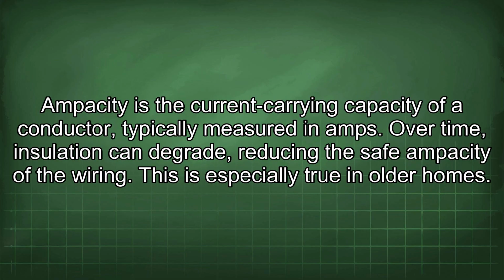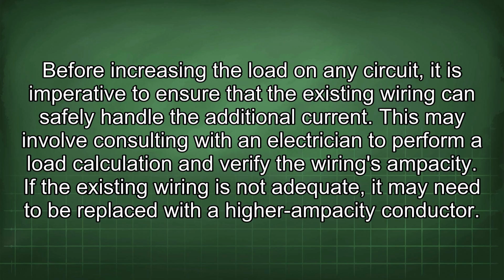Ampacity is the current carrying capacity of a conductor, typically measured in amps. Over time, insulation can degrade, reducing the safe ampacity of the wiring. This is especially true in older homes. Before increasing the load on any circuit, it is imperative to ensure that the existing wiring can safely handle the additional current. This may involve consulting with an electrician to perform a load calculation and verify the wiring's ampacity. If the existing wiring is not adequate, it may need to be replaced with a higher ampacity conductor.